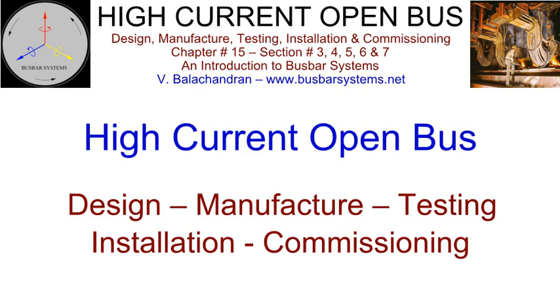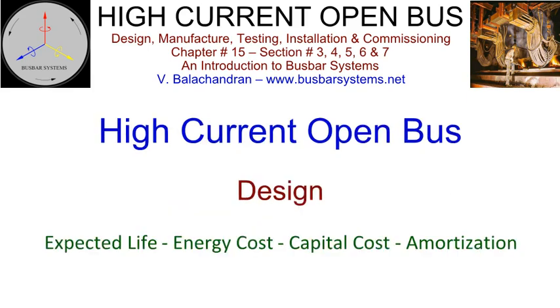High current open busbar: manufacture, testing, installation, and commissioning. Design. The layout of the busbar system, for most of the industries that operate on high current low voltage, is very much standardized. The entire exercise reduces to making the current carrying path as short as possible. Once that has been achieved, the voltage drop and power loss can be reduced only by increasing the cross-section of the conductor in DC systems. In AC systems, additionally, the skin depth and conductor spacing also need consideration.